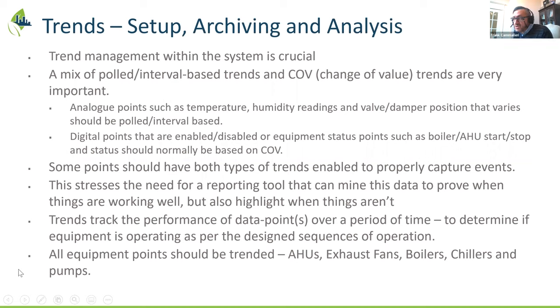The types of trends that should be in place: basically all key equipment points should be trended—air handling units, fans, boilers, chillers, and pumps. These days it's real important, especially for the big equipment: air handling units, boilers, and chillers in terms of priority. But it's not that difficult, once you demand it of your service provider or manufacturer during installation, to get them all set up, because they come in very handy afterward.